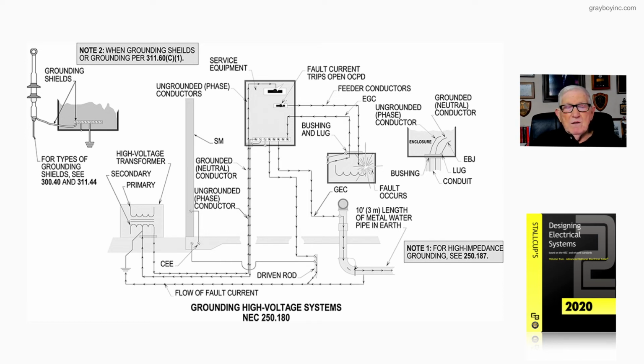and complying with 250.180. But now notice for lightning protection, diverting surges, lightning protection, and things of that nature, you'd want to review 250.4, A as in apple, 1. And then if you high impedance ground, in other words, you're going to put a high impedance ground in your grounding system somewhere, then you'd look at 250.187. Now I think that pretty well covers what this figure 17-22 is trying to point out to the user of the NEC.